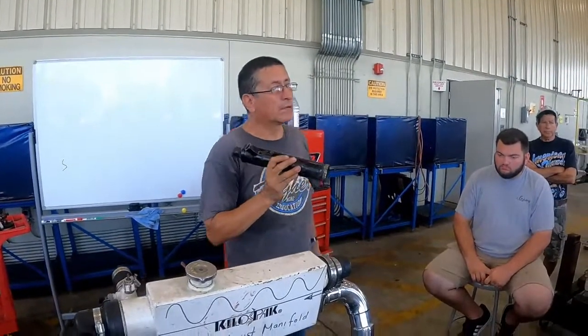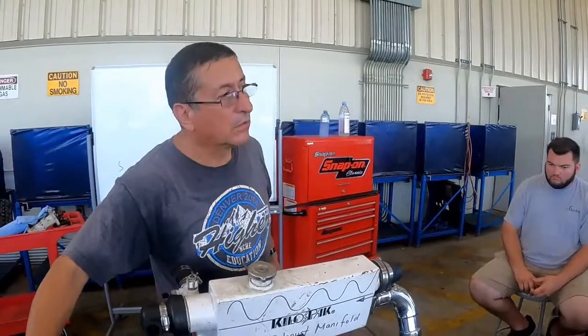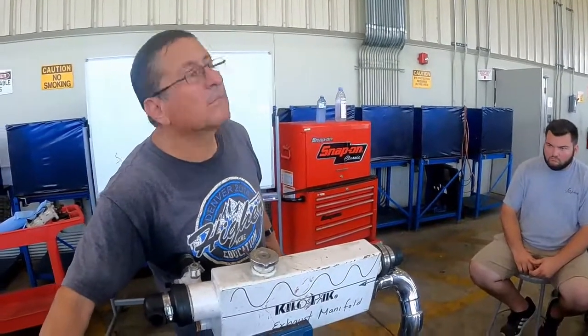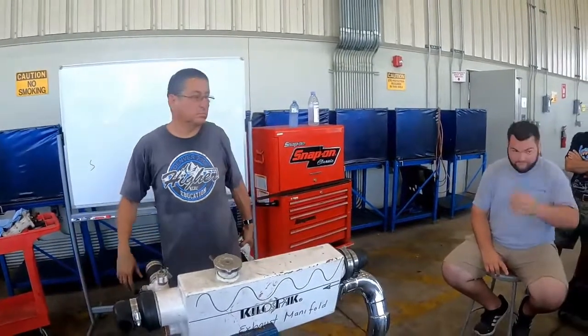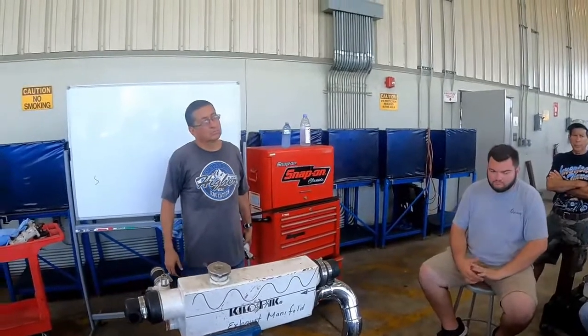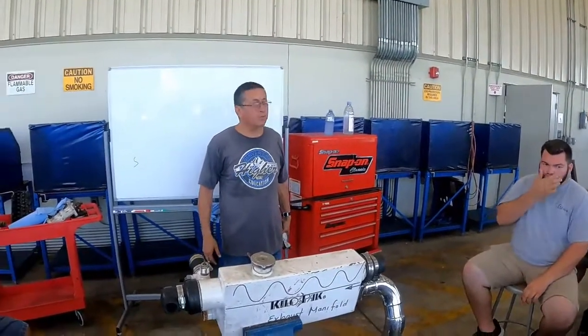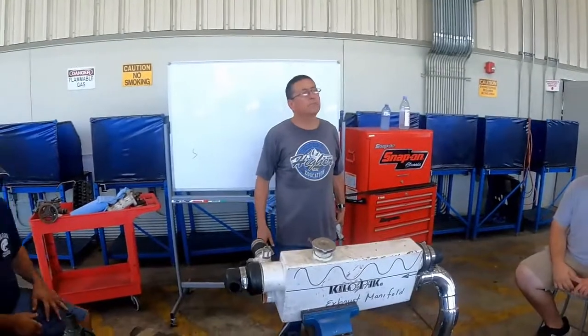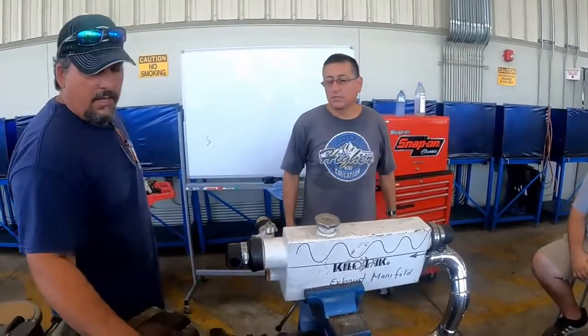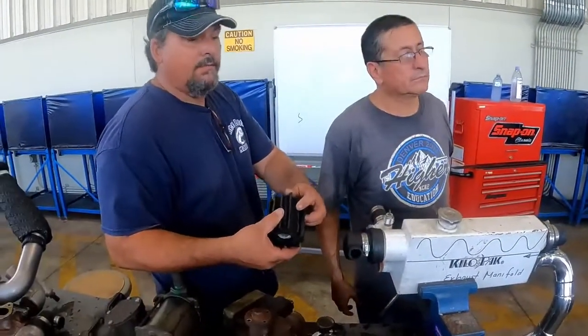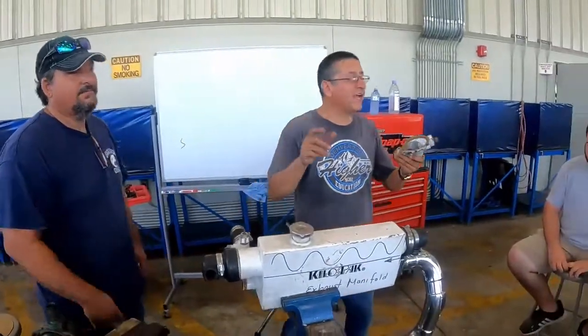So couldn't that be another cause of your coolant being too hot and bubbling, if it's not getting any water through? Absolutely, because it's clogged. But wouldn't it be able to overheat without you having a leak in your coolant? Correct, that's possible. That's why you have to check the whole system. Also, these get clogged up if pieces of the impeller break off. That's the next one.